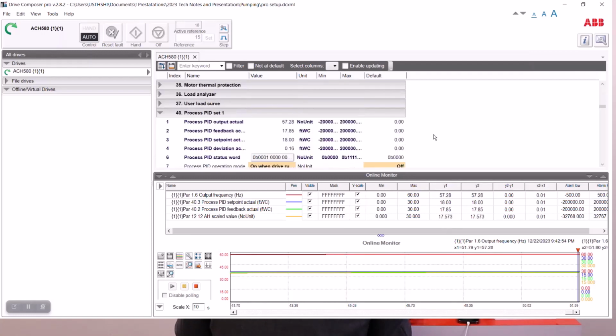When I look at my numbers here in my PID process section, here's where these numbers are coming from. The output actual is the output frequency that the drive's expected to run at, and here's my set point, and here's what my calculations are right now. And it's stabilizing. It will eventually get itself up to 18, and these numbers will get closer and closer.